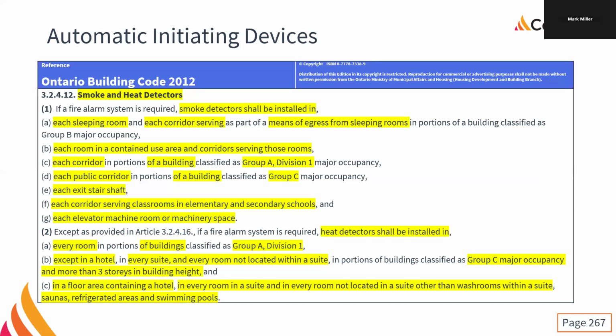So we go back to 3.2.4.12 in the building code. If a fire alarm system is required, smoke detectors shall be installed in the following places. Last week we looked at where we put heat detectors and fire detectors. If they call for a fire detector, we can put in a smoke detector, because a smoke detector is a valid fire detector. Generally speaking, we don't, because of the costs involved. Smoke detectors are much more expensive. Heat detectors are cheap, so we throw those in wherever we can.